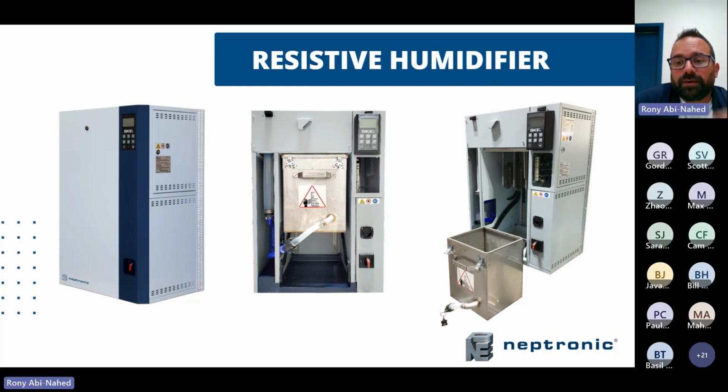So every 4 to 6 hours, it will drain and refill with fresh water to try to minimize the scale building inside the tank. During this process, during the draining and refilling cycle, you lose your set point. So if you want to always be precise, that plus or minus 1%, you need to put an RO system before the unit. Now the unit doesn't have to drain because it's pure water getting through it. So it will keep running the whole time. And that's how you can achieve precision in critical applications.